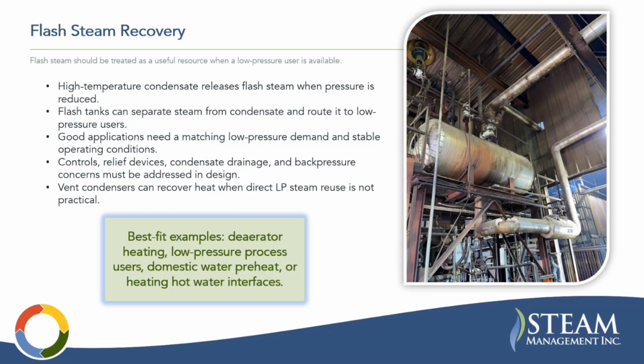Flash steam recovery. There are a couple of different ways to recover energy from flash steam. But one is to reconfigure a system with a pressurized condensate tank. So say you have a 100-pound steam system, and the condensate is coming out at 100-pound saturation temperature. When that gets to your atmospheric tank, it's going to flash off a significant amount of steam, I think, for 100 pounds, like 12, 13%, something like that.